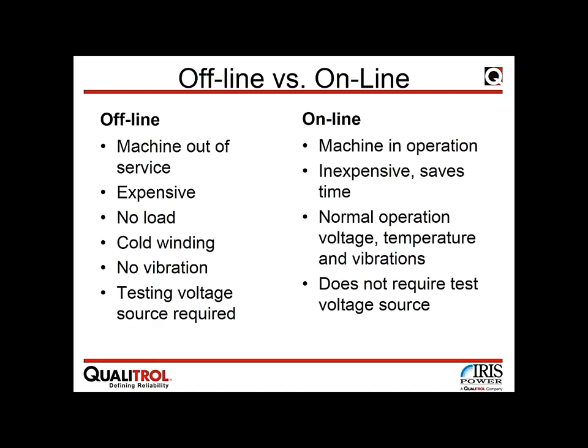Comparing offline and online approaches: with online testing the machine remains in operation, while offline testing means the machine is not generating revenue. From a technical standpoint, offline tests also lack load, and consequently temperature and vibration are absent. Online monitoring captures data in operational mode with all those parameters present, which makes a major difference.